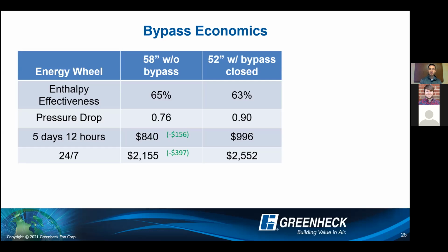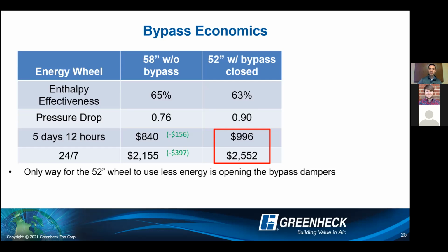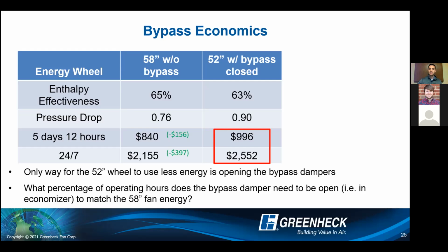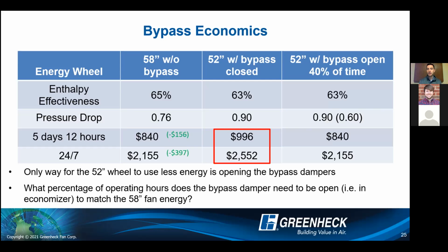Looking at a 5 days a week, 12-hour a day application versus 24/7 with the 58-inch wheel, this is specifically looking at fan energy savings. You can see the cost it would take to operate that fan. It's about a $156 reduction in the first situation, and if it's 24/7, about a $400 reduction in fan energy operation per year. Now, the reason you want wheel bypass is during economizer, right? So when the wheel bypass is open. But how often would it need to be open to actually make up those energy savings during normal operation? Our study actually showed about 40% of the time. And that assumes a 50% reduction in pressure drop with that bypass open, which is actually pretty aggressive.